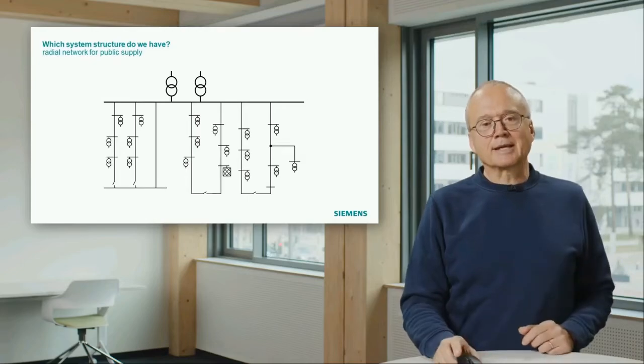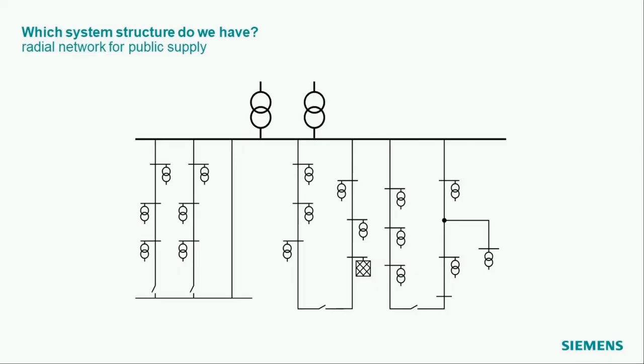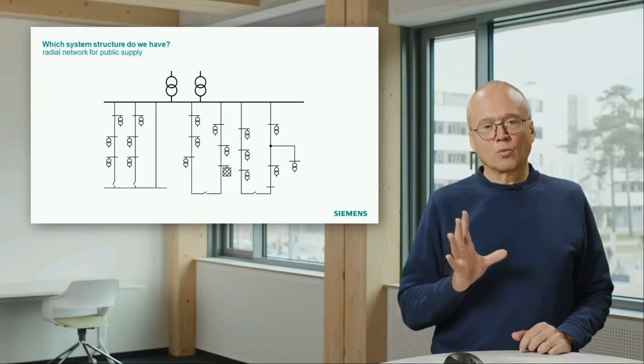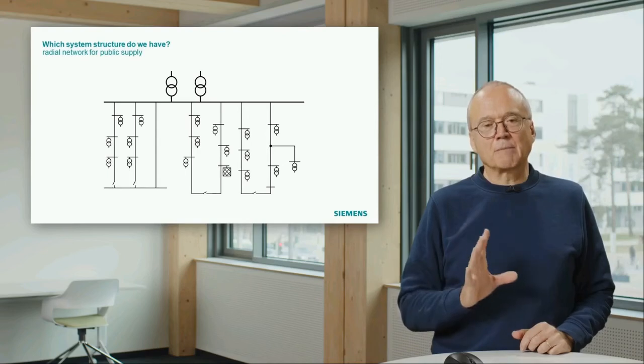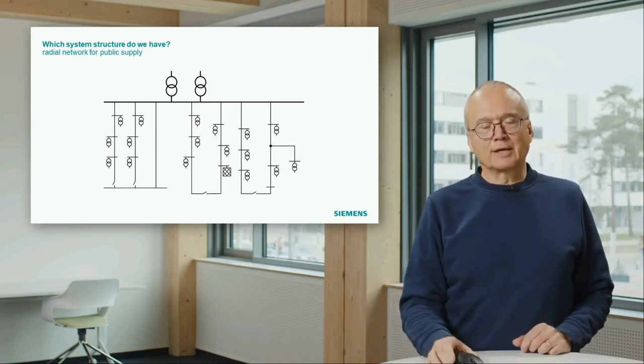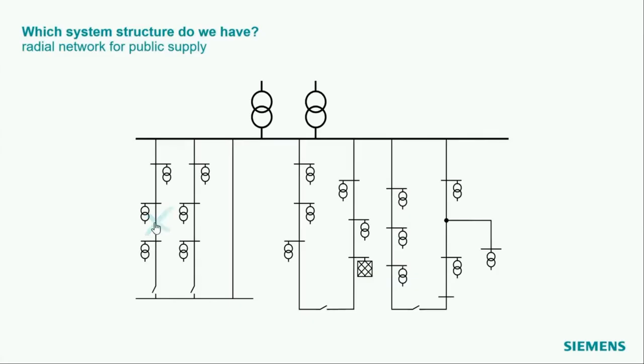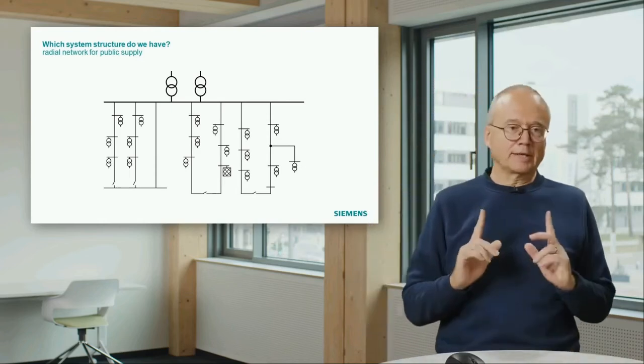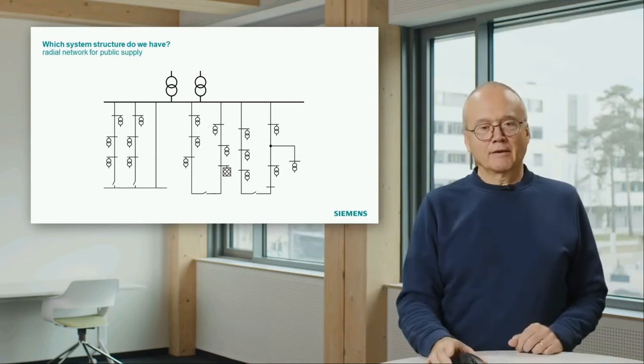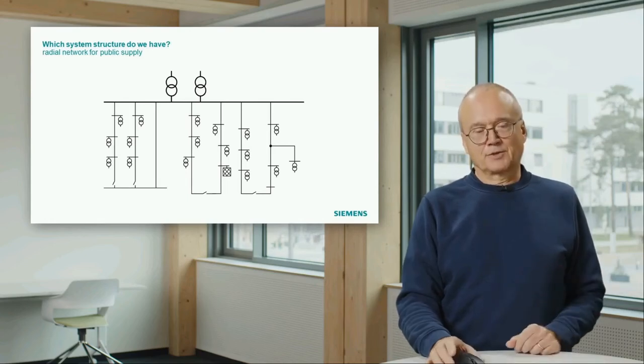And the important thing is that these feeders are radial. That means on the bottom here, these connections are open. That means we have a system with no meshes. The system is radial. And the important thing is, if you have a short circuit on one cable, for instance on this cable, the short circuit current comes through the transformer, the busbar, to this cable. It comes from one side, and that is a very important feature when we design the protection system.